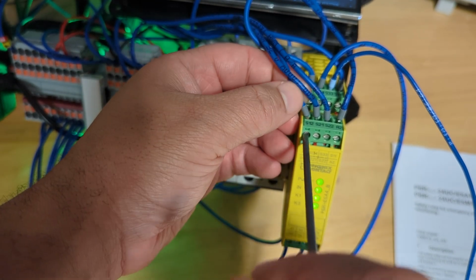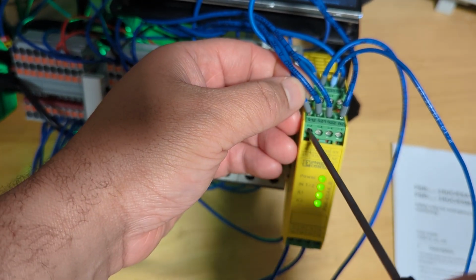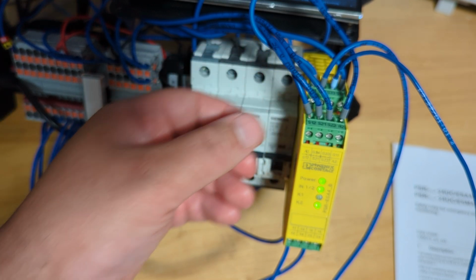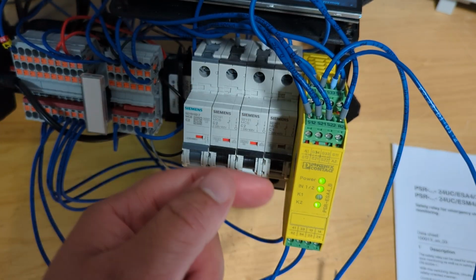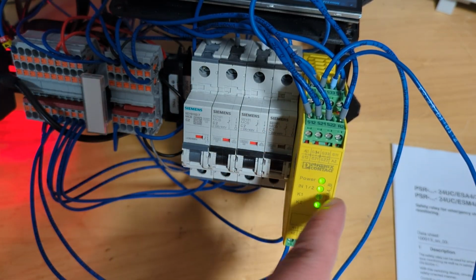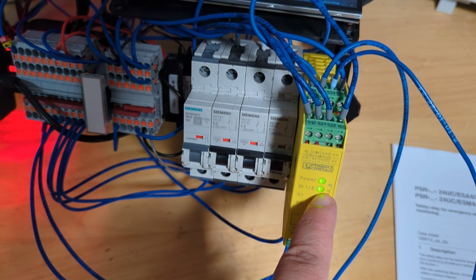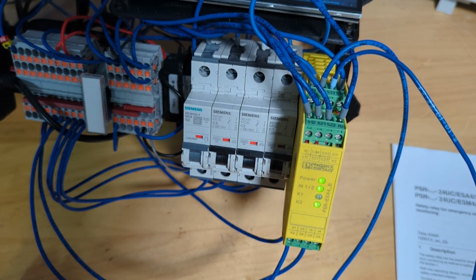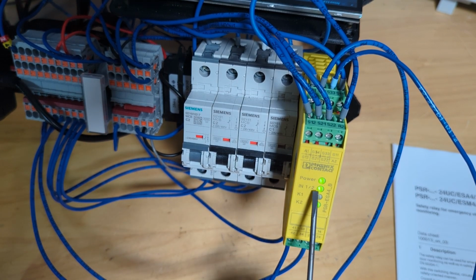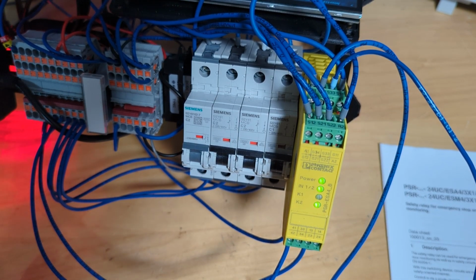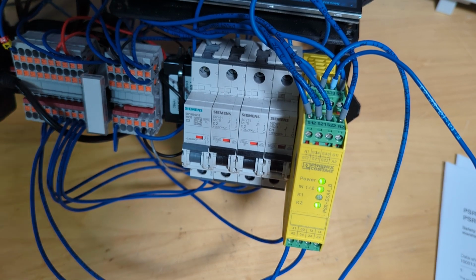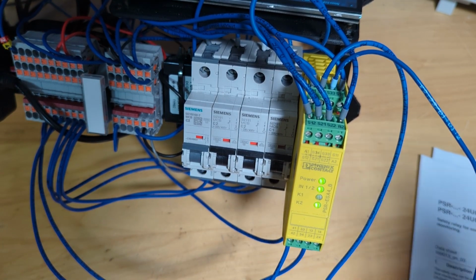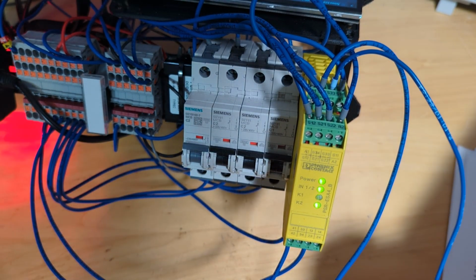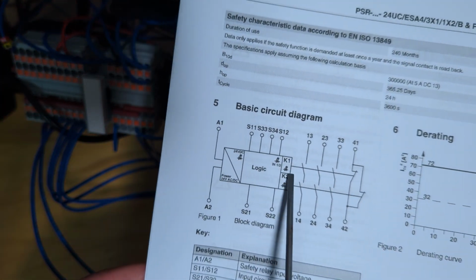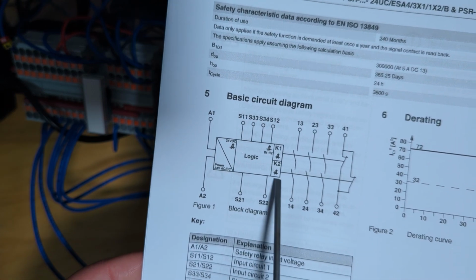disconnect, let's just take out S12. Just there, it detected a fault. So it's made connection again, and it says, okay, your inputs are good again. But the output K1, maybe I should show you the schematic of this. Inside the safety relay I've got two relays, two contacts that are opening and closing. So K1, which is this set of contacts, and K2, this set of contacts.